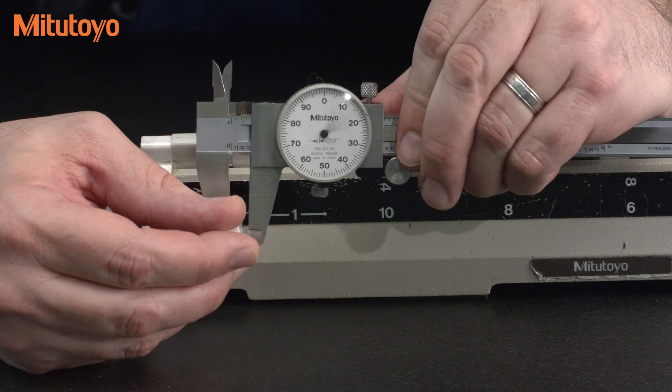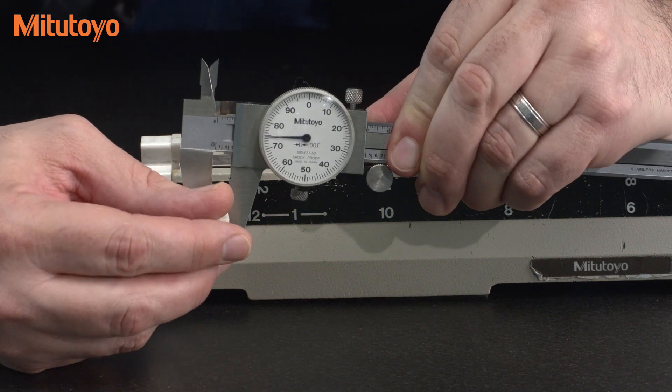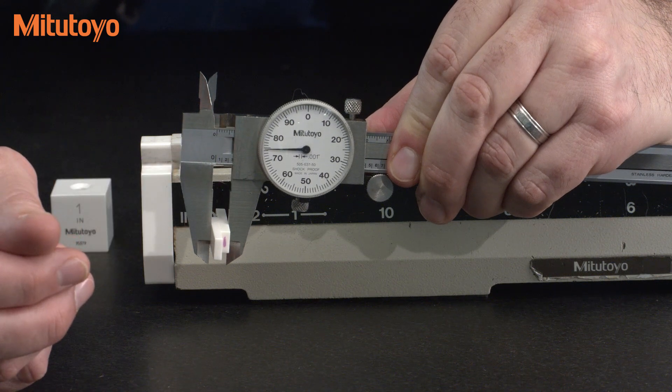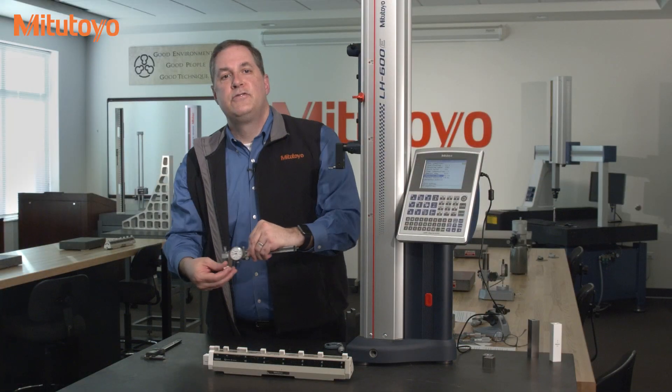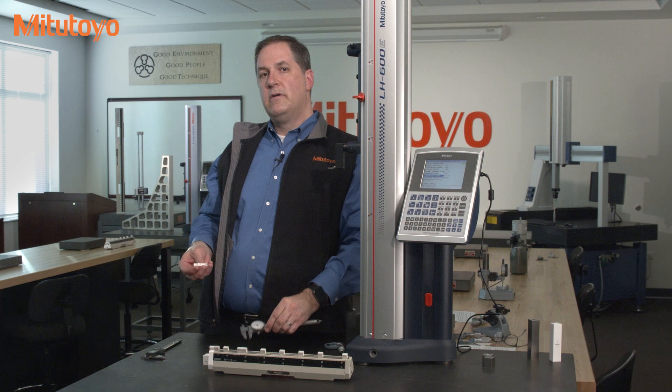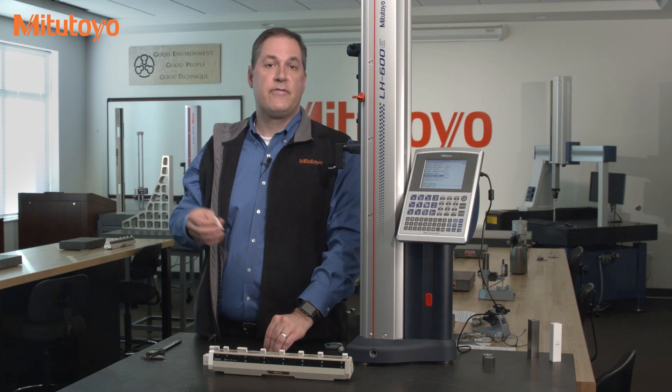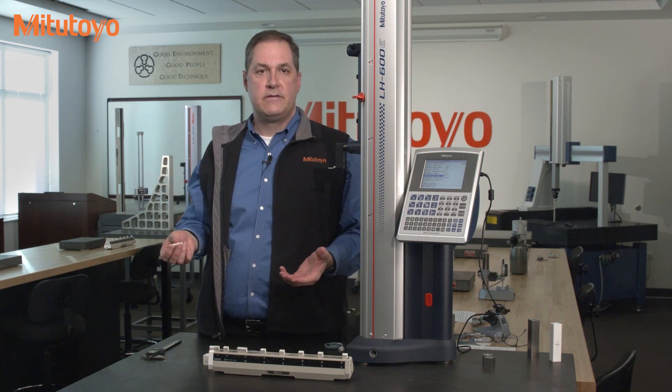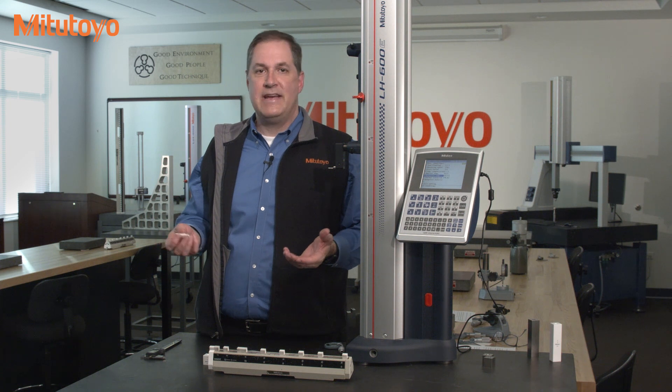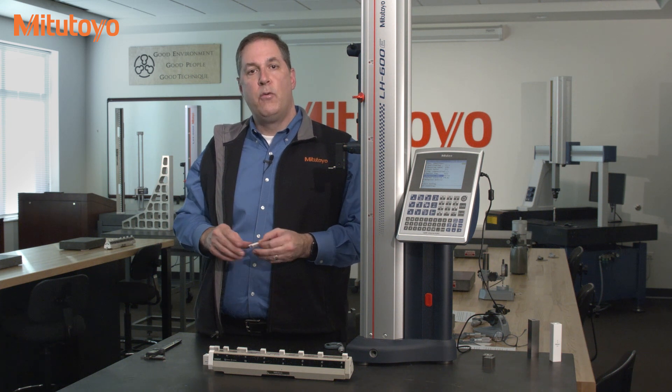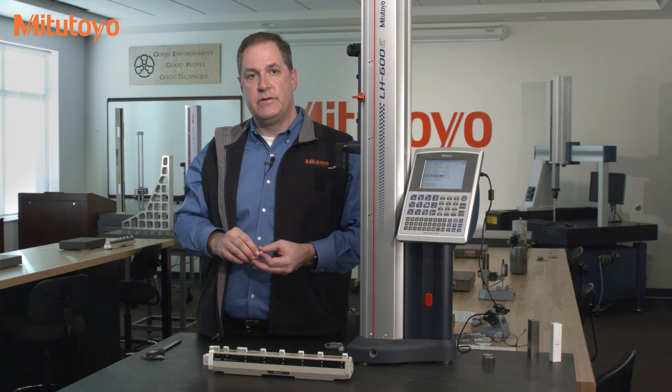And if I measure both blocks that are rung together, I should be at the nine o'clock position. So these two gauge blocks, rung together, give me three additional easy test points. Not too difficult to test the accuracy of the caliper with the pointer in different angular positions.